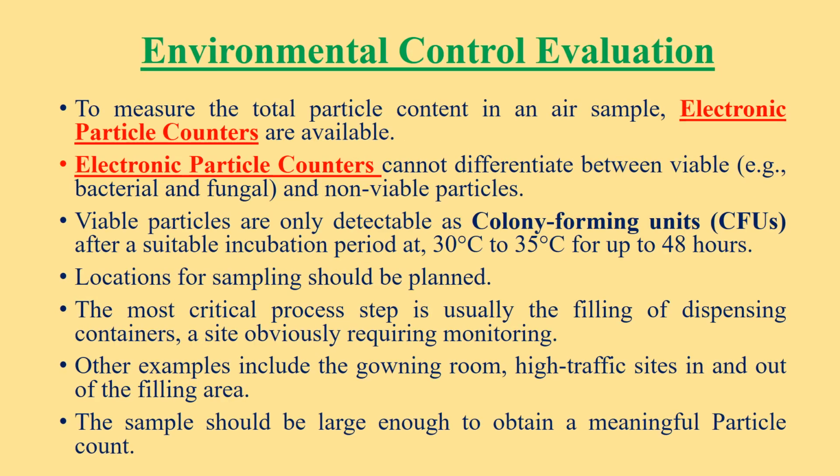Next is your environmental control evaluation. To measure the total particle count in an air sample, electronic particle counters are available. Electronic particle counters cannot differentiate between viable and non-viable particles. Viable particles are only detectable as colony forming units after a suitable incubation period at 30 to 35 degrees centigrade for up to 48 hours.